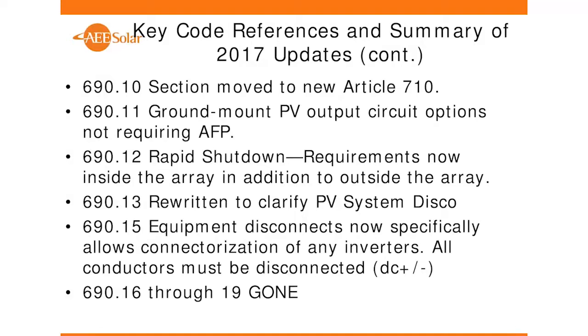One of the justifications for it is that we really don't have any arc fault detectors that work at, or that are even built for, larger 100, 200, 300, 400 amp circuits. They don't exist yet. And that's not the predominant place where we see our arc faults. The vast majority of the arc faults are on the small side of the system. So it gives a little breather to the ground mount world for areas that are required to meet that.